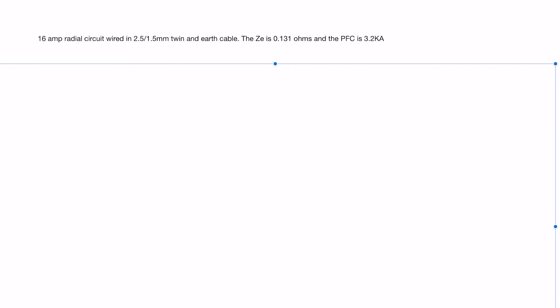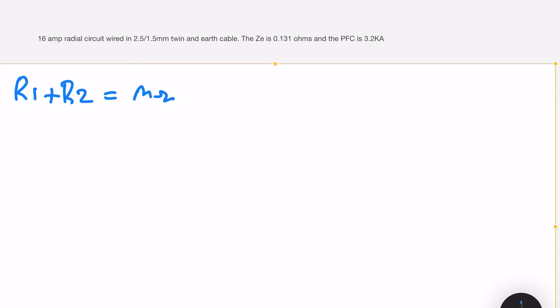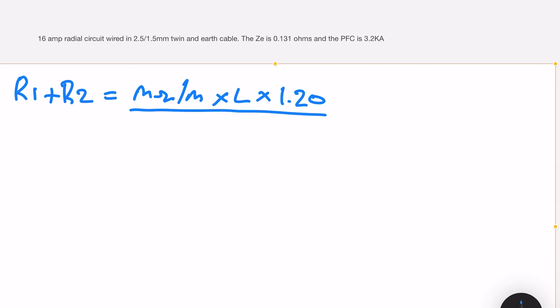Now doing the same thing for the fault current. The first thing we do is calculate R1 plus R2. The difference from the short circuit calculation is that we now have a reduced size CPC. So we take the values for milli-ohms per meter for the 2.5 and 1.5 from the on-site guide — that's milli-ohms per meter multiplied by length multiplied by the correction factor of 1.2, divided by 1000. It's the same equation but with the different value for milli-ohms per meter due to the reduced size CPC.